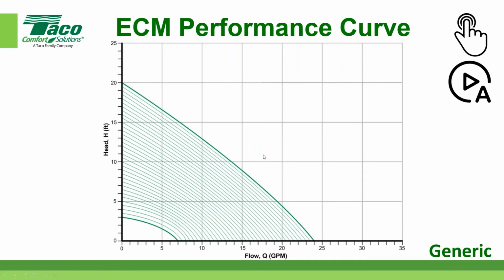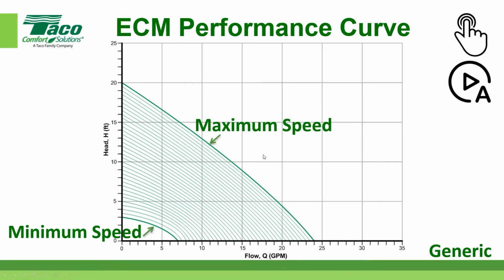What I want you to get your arms around is this. Look at what an ECM performance curve is, or a high efficiency circulator has the ability to do cool things like this. And Taco takes good advantage of this in a lot of ways that our competitors did not do. They're going to be copying us. It's just a matter of time, because these are things that we can do and they can't. So they're going to kind of up the ante. We up the ante, and now they're jumping in with both feet. What's more important, rather than maximum speed and minimum speed, is everything in between. Now they have the ability to turn themselves up and down in automatic modes, or in a manual mode, you have the ability to just turn it down. Okay, and that's what we'll talk about here.